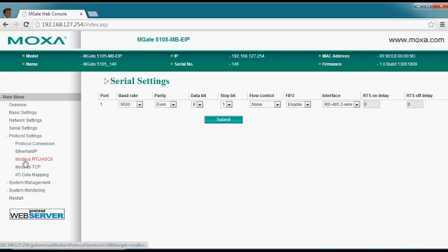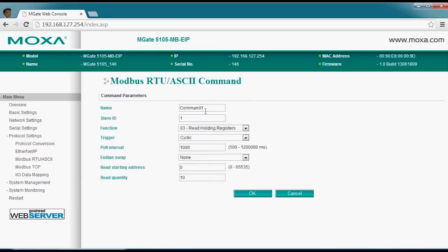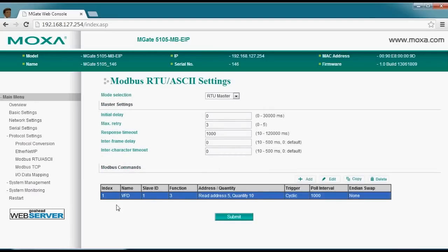We'll go ahead and define the values we want to look at from the PLC — click on Modbus RTU. The MGate is going to be a master. We're going to add some registers to pull; let's call this the VFD. We're going to read data starting from register five and read 10 registers, then submit these for a polling cycle. At the bottom of the screen you can see we'll pull this data every 1,000 milliseconds — one second — though you can change that if you prefer.